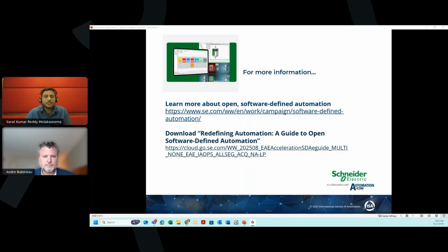I do want to define the application behavior. I want to define my control program first, and I want to make this control program resilient enough to work on any hardware, which means irrespective of what type of IO I am using, irrespective of what type of physical connectivity I am using. I want my program to be defined in such a way that I'm able to choose the hardware at the end. And to me, this is what software defined automation is, and this is where we are progressing, especially with the 61499 standard. At a high level, we call this a top-down approach instead of bottom-up.